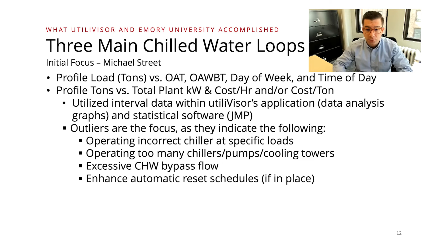And then they did have some basic reset schedules, which we improved again based on the season. I'll tell you, everybody can talk about efficiency metrics and kW per ton, but this actually was a little misleading when we first started collecting data, because at part load conditions the efficiency seemed really, really good. The plant was running a larger machine that was the most efficient compared to some of the smaller ones.